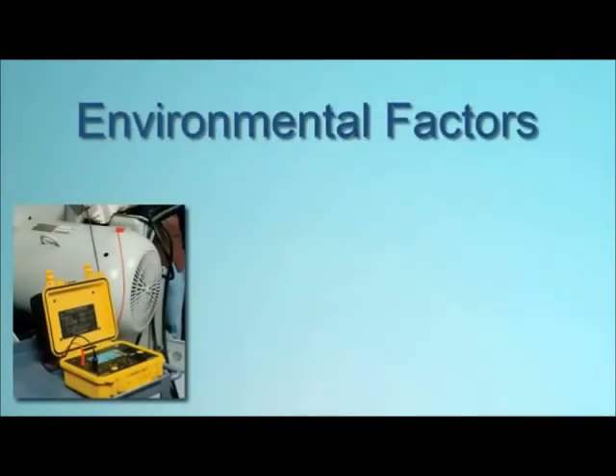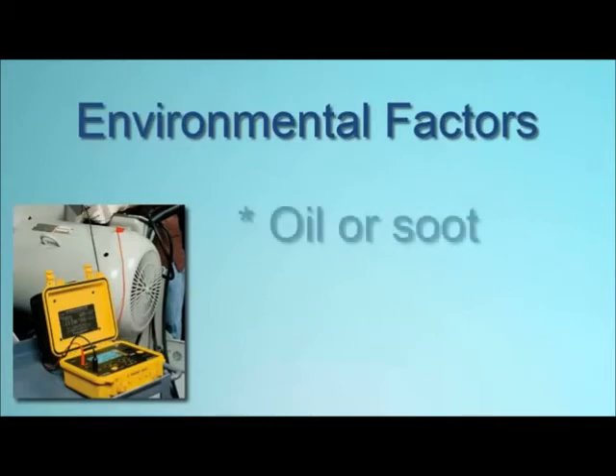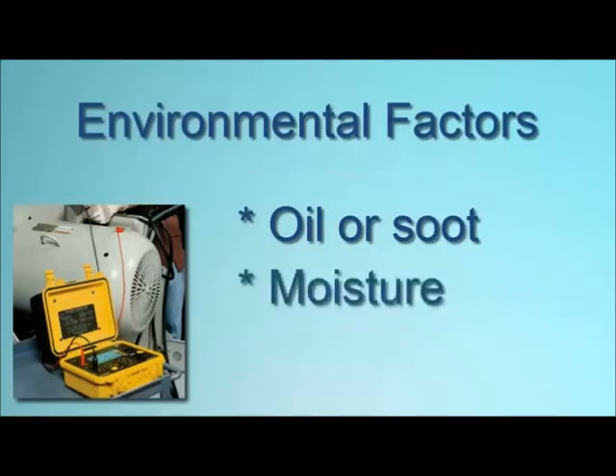It's also important to be mindful of how environmental factors can affect resistance. For example, oil or soot on the equipment's surface can lower insulation resistance. If any of the equipment's surface temperatures are at or below the dew point of the ambient air, moisture forms, which can significantly lower the equipment's resistive value.